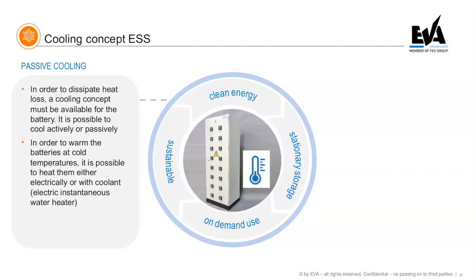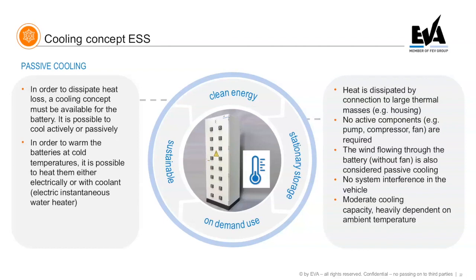Then, in order to warm the batteries at cold temperatures, which is quite necessary, it is possible to heat them either with electricity or with coolant. This would be shown more actively on the other slide. It's important to warm them, especially here in Germany in the winter, or depending on where you put the stationary battery system. It's required because batteries don't like being under zero degrees, as charging the cells is particularly damaging. To have a safe operation level, you have to make sure that you have the right temperature level at all times. With passive cooling, you can connect to large thermal masses, for example the housing. This can be an advantage. This is something that you have to take care of.